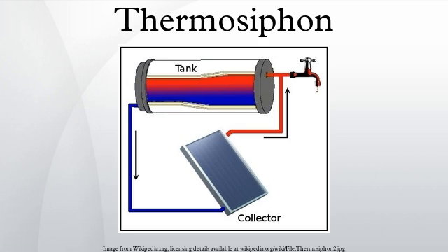The thermosiphon has been sometimes incorrectly described as a gravity return heat pipe. Heat pipes usually have a wick to return the condensate to the evaporator via capillary action. A wick is not needed in a thermosiphon because gravity moves the liquid. The wick allows heat pipes to transfer heat when there is no gravity, which is useful in space. A thermosiphon is simpler than a heat pipe.